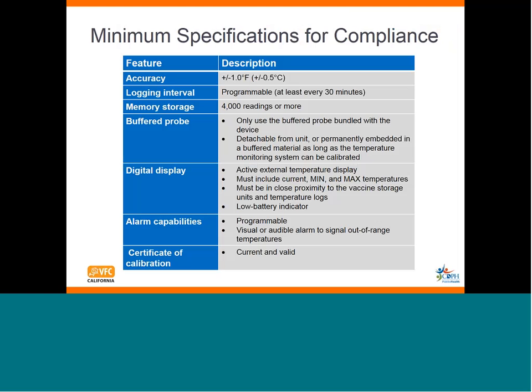And to help guide you with this compliance, we wanted to let you know what the minimum specifications are for a digital data logger. Any temperature monitoring systems utilized must meet all specifications listed here in order to meet VFC program requirements. Temperature readings from monitoring devices that do not meet these requirements, and yet you have valid certificates of calibration, still cannot be considered valid and used for the determination of vaccine viability.